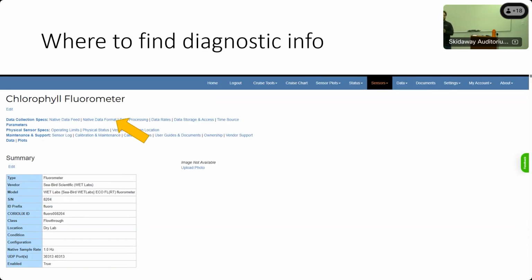So this is the string of numbers and letters and words that come out of the instrument raw and how to interpret that. So the 1286, 1287, what those actually mean and how to translate it. Really helpful if you have to go back to the raw data because you might need to, say, apply a new correction.